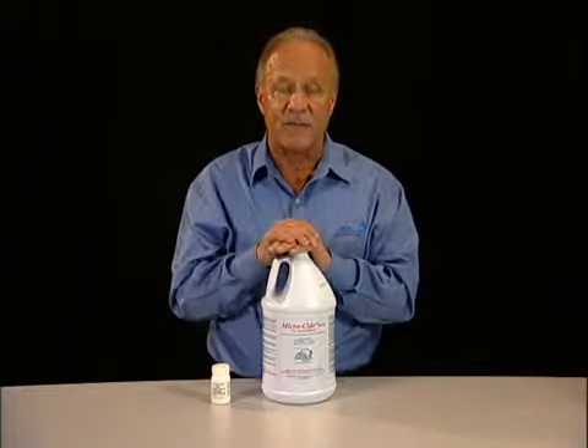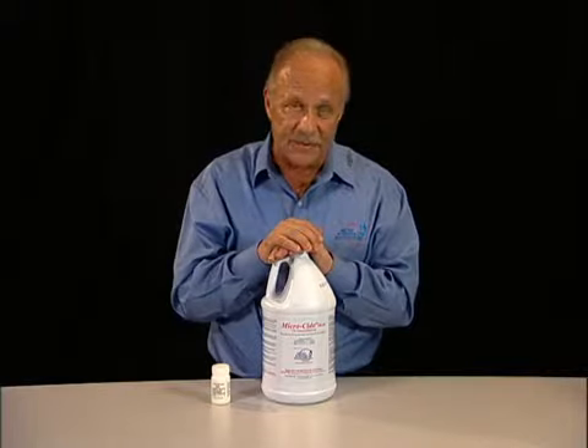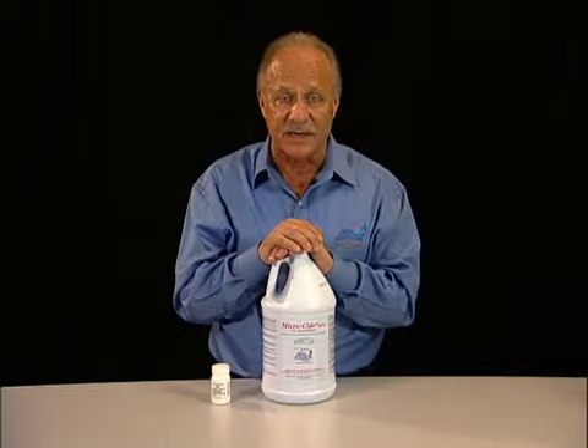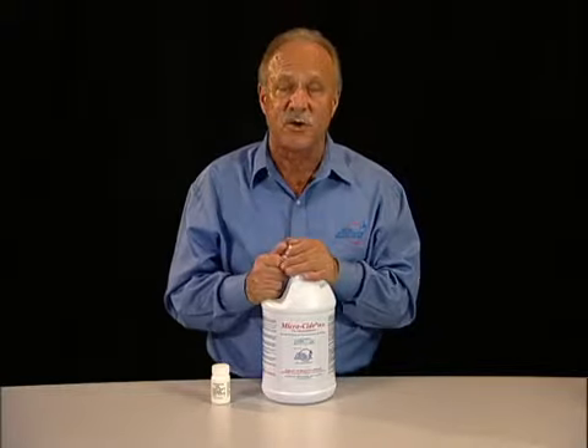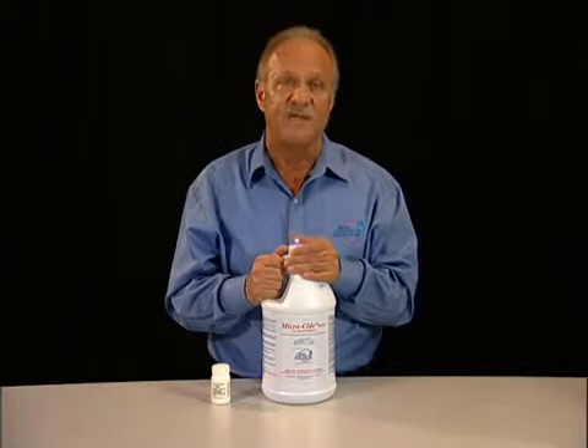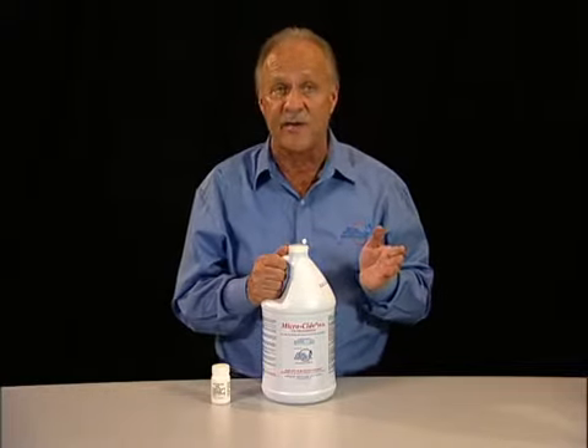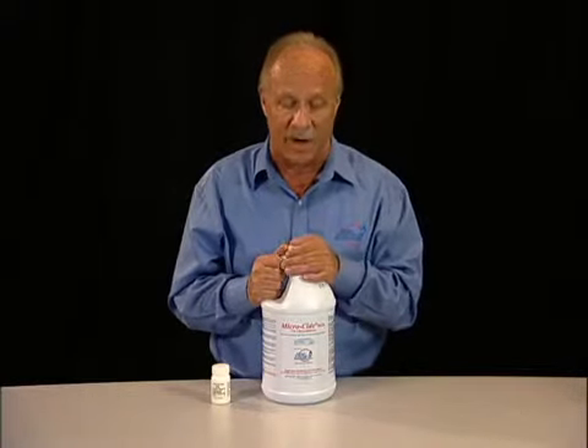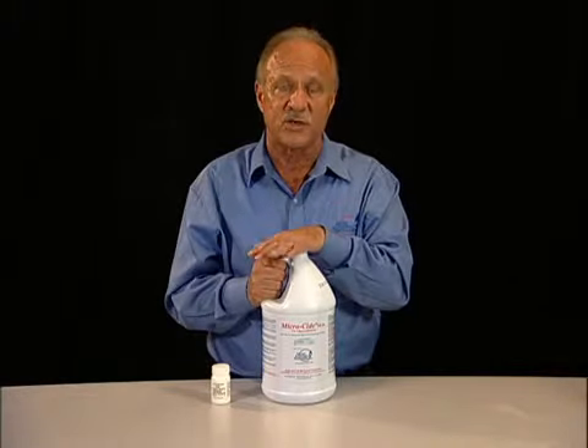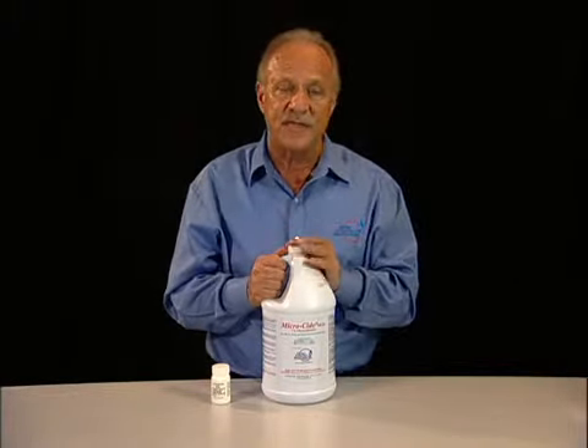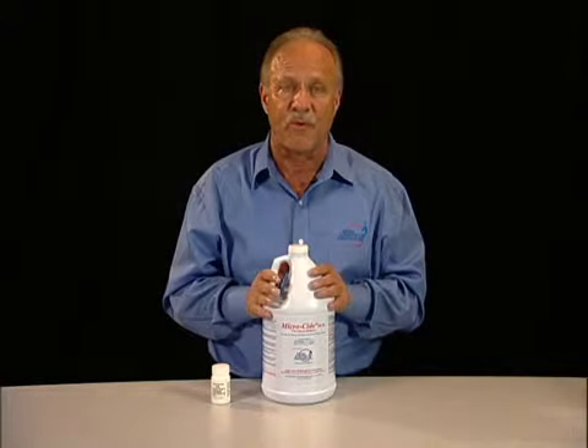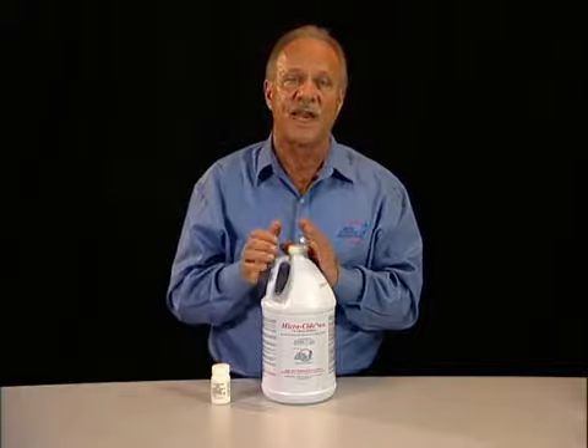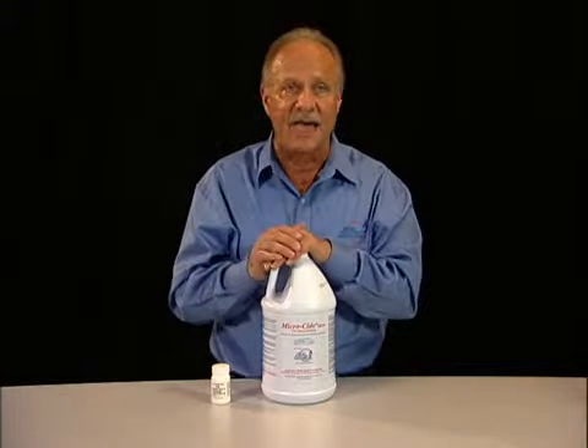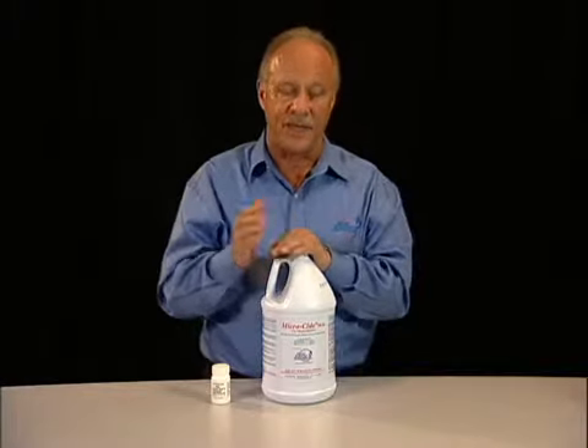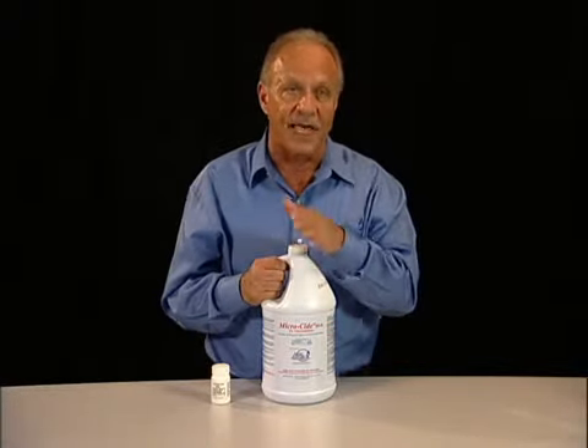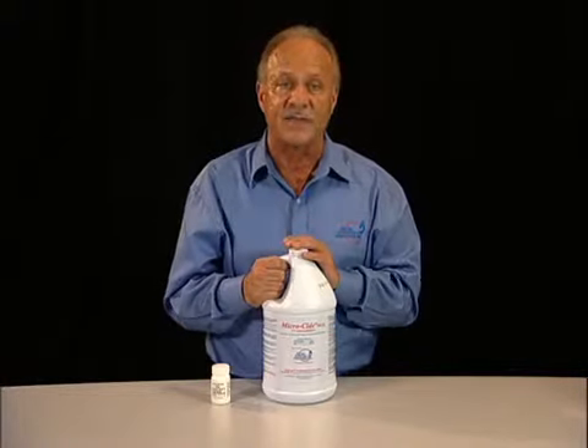Now, if you would contrast that with this product, which looks, tastes, and smells the same as the Cidex product and the Microcide product, this product has a total of a 25-minute soak time and is valid for use up to 28 days on the condition that you monitor it each day like you're supposed to do with all glutaraldehyde products. The advantage is that a 25-minute soak time puts the user into a situation where they are using the product in an appropriate manner by soaking the scopes for less than a half an hour, which, let's face it, probably 95% of the GI labs in the industry are soaking their scopes for less than 30 minutes. And this puts them in compliance with the FDA.